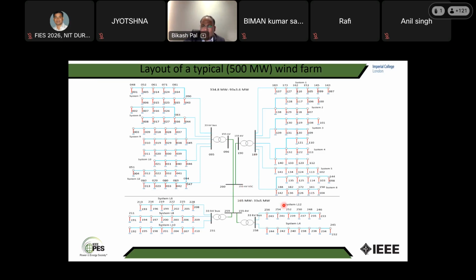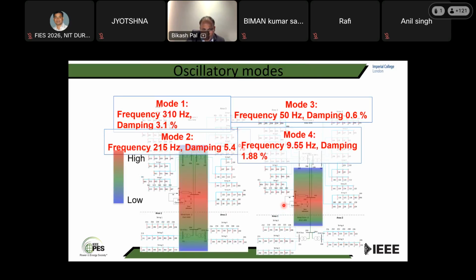On this side, we again take operating conditions for linearization and get the eigenvalues. And you see there are 4 modes: 310 Hz, 215 Hz, 50 Hz, 10 Hz. These modes are all more than 2 Hz, so an EMT model was the only way. Everything was modeled by EMT. Each wind turbine has about 30 to 40 differential equations, including its control, gearbox, rotor, turbine, pitch control.